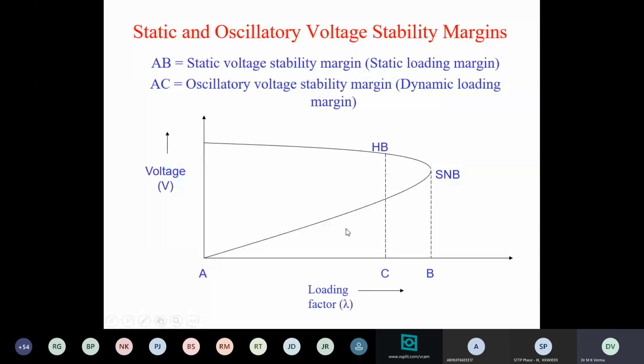This curve is popularly known as the nose curve. The nose curve is a plot between voltage magnitude and loading for a bus, and once you increase loading, you see voltage is decreasing. A point comes beyond which you cannot load. There is no solution. So this point is called saddle node bifurcation. Before saddle node bifurcation, there are two solutions. Now this solution is stable and this is unstable. Why unstable? Because if the system goes to this region, then voltage becomes uncontrollable. Both voltage and power become uncontrollable, and that may cause cumulative decrease of voltage.